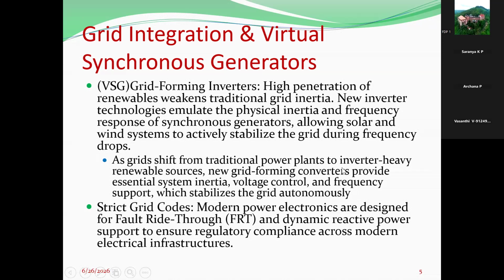As the grid shifts from traditional power plants to inverter-heavy renewable energy sources, new grid forming converters provide essential system inertia, voltage control and frequency support, stabilizing the grid autonomously, without manual control, as per the requirement on the consumer side.